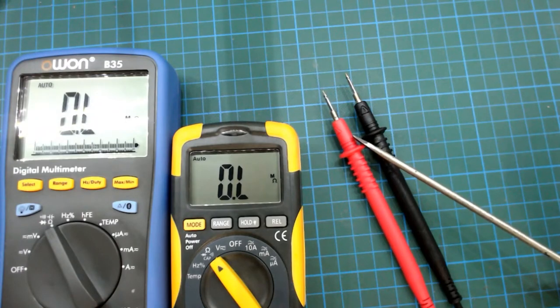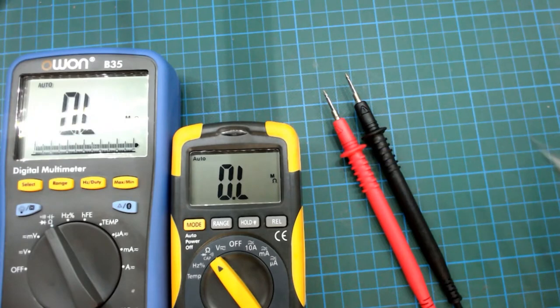A continuity test doesn't necessarily mean that there's a short between two points, although that is quite normal. It could also mean that there's very low resistance. Most multimeters will say something around 5 ohms is considered continuity. Anything less than that and it will tone.